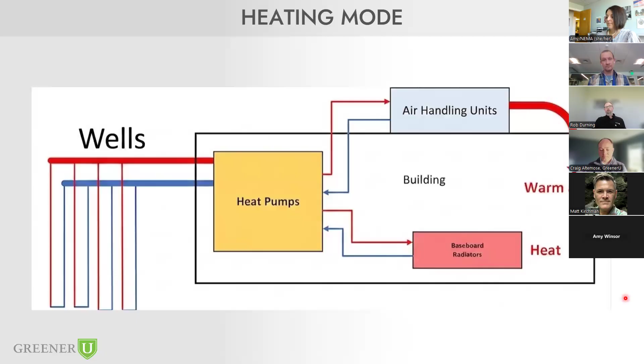We illustrate both scenarios here, because in a recent conversion that we did for a church in Wellesley, Massachusetts, we were able to reuse a lot of the existing infrastructure in the building. We were able to reuse the coils in the VAVs and the baseboard radiators around the building, even though they were originally designed to handle 180 degree high temp hot water that would have come from your boiler system. Instead, we added air handling units up on the roof and connected to existing ducts to basically carry more of the heating load up here, because it was less disruptive to all the spaces down here. And so we were able to do this retrofit while maintaining occupancy through the building, keeping most of the construction up here, down here in the basement where we were out of sight, out of mind, and up here on the roof. Obviously the drilling was impactful from a site perspective, but as long as we could maintain safe ingress and egress to the building, we were able to do that in an occupied building.